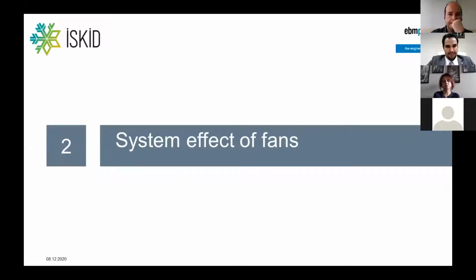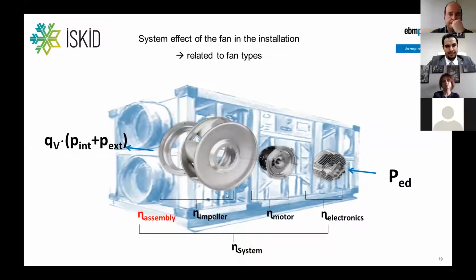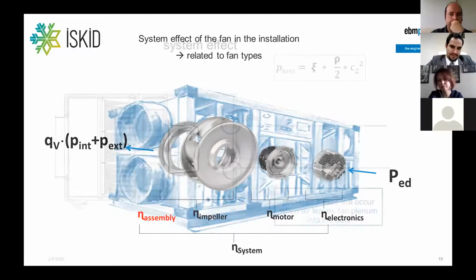System effect of fan. So the fan manufacturer can take care of, let's say, the fan system efficiency, but the assembly can also be expressed by some kind of efficiency, ETA assembly, I call it here, and this is related to the installation of the fan in the unit. Every fan manufacturer shows this kind of efficiency in the documentation. Some of them only show the fan efficiency because they don't add the motor, but in almost no documentation do you find the installation losses to the system.